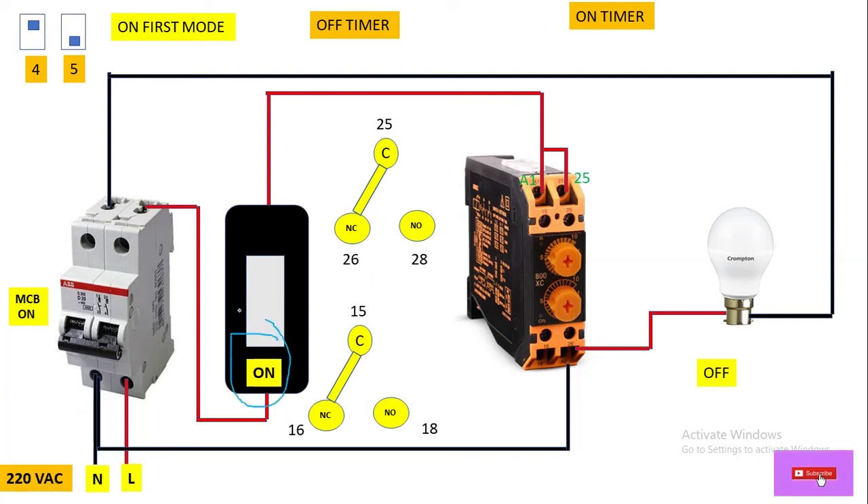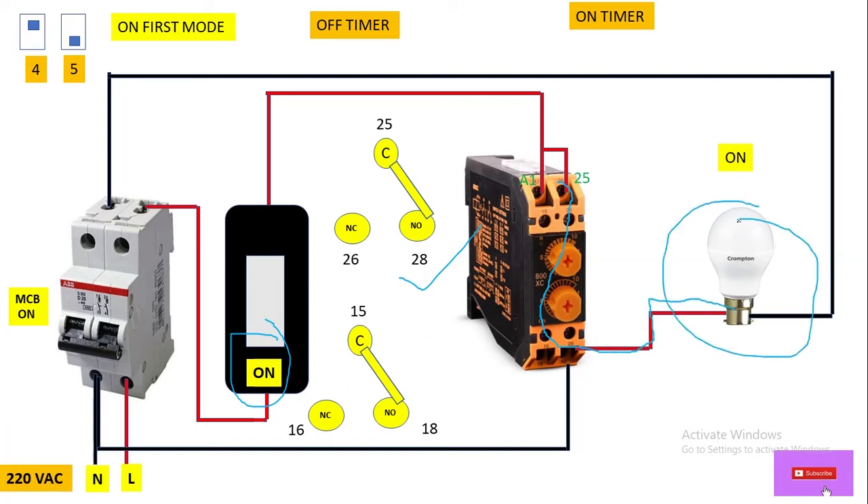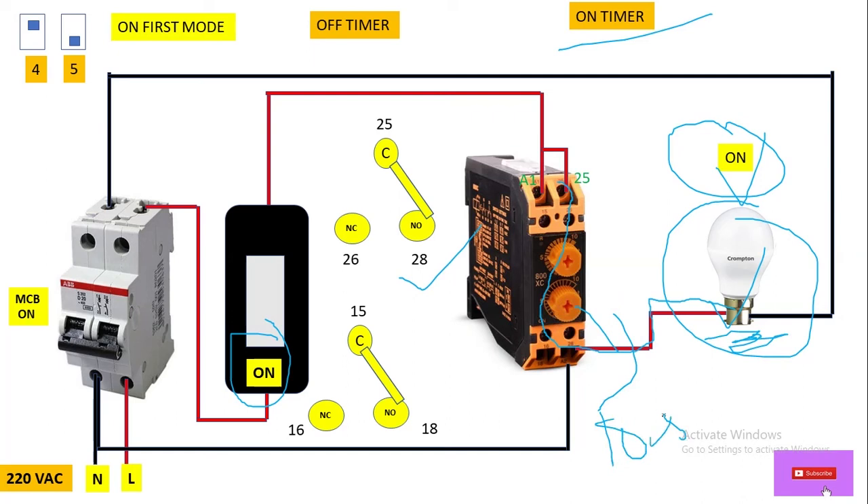In on first mode, when we switch on the switch, the relay activates immediately — its relay contact gets changed and the bulb glows right away. So when we switch on the switch, the load turns on immediately. As you can see, terminal 28 is NO, so from terminal 25 power flows through terminal 28 and reaches the load. This bulb will remain on up to its on time setting, which is 10 seconds.